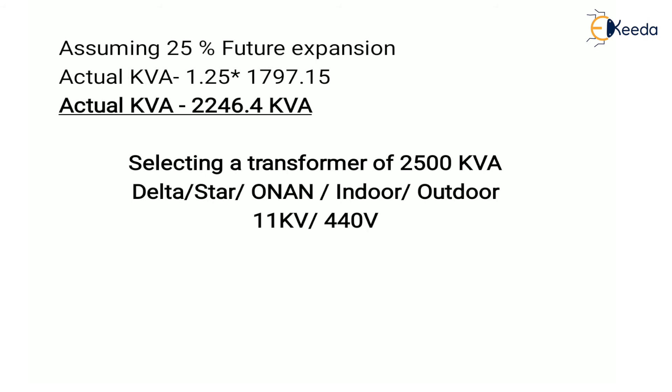Based on this actual KVA value, we select a standard transformer rating of 2500 KVA. As it is a distribution transformer, it will be delta-star connected, with ONAN (oil natural, air natural) cooling, suitable for indoor-outdoor installation, and will be a step-down transformer of 11 kV / 440 V.